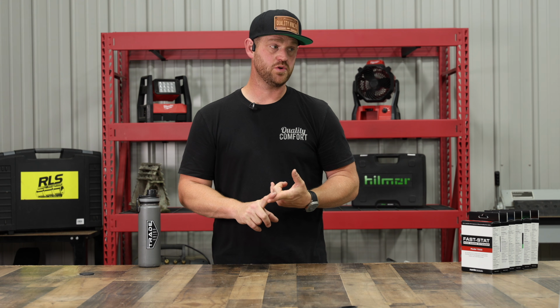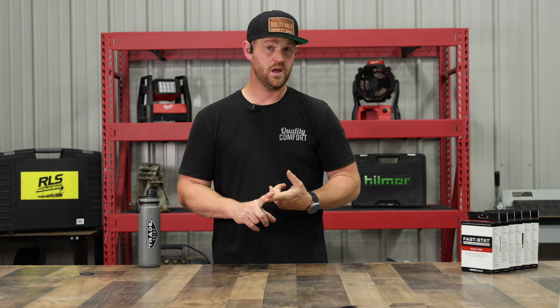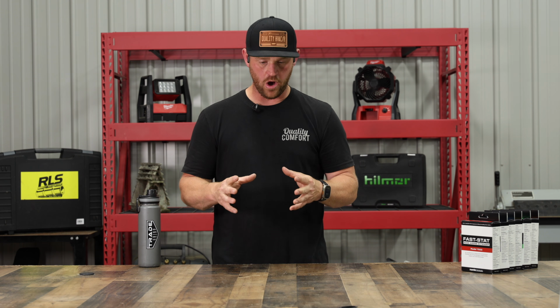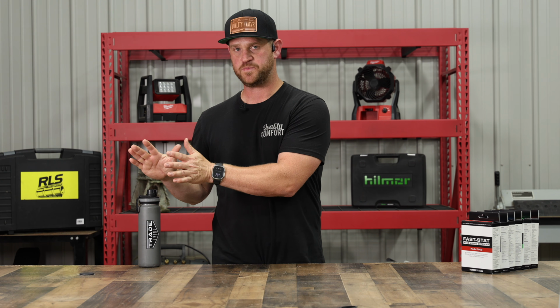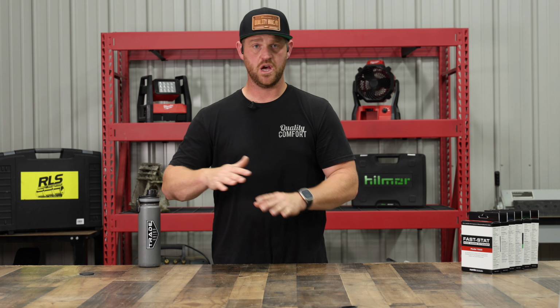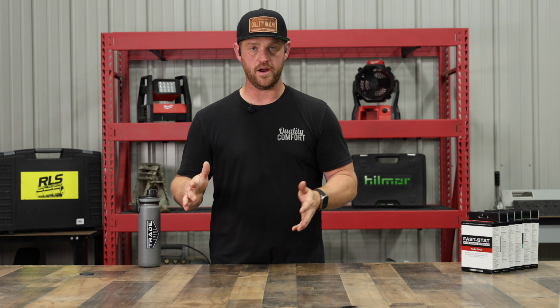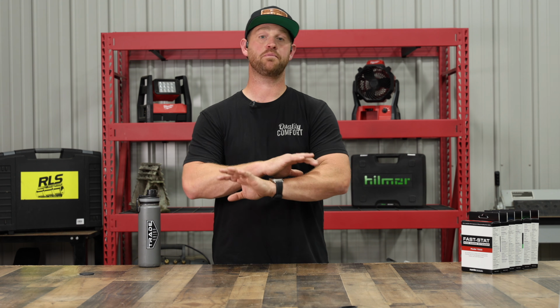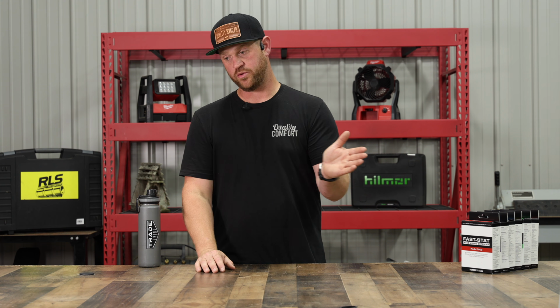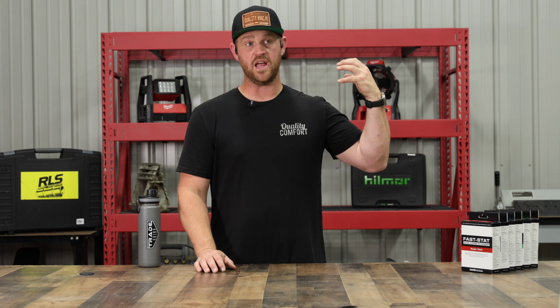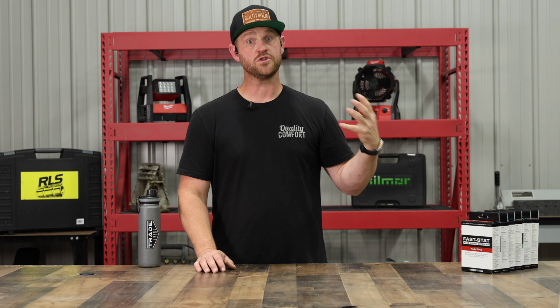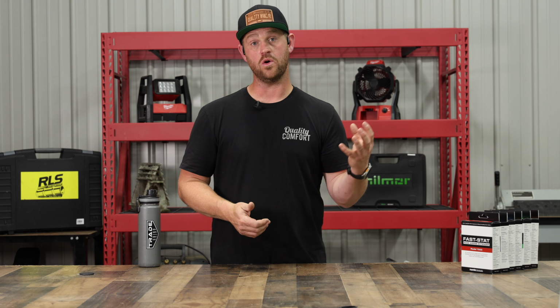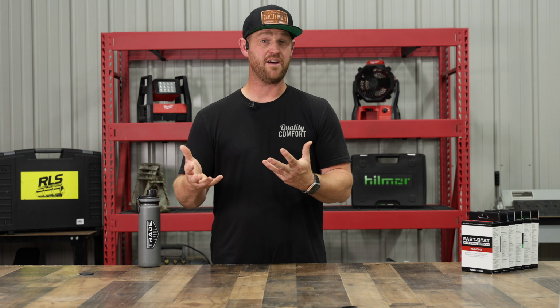So going back, you have 24-volt controlled, we have communicating, and we also have what they call VRF. Now we're only talking about variable speed systems, right? Because single stage and two-stage are pretty straightforward, not a whole lot to talk about there. With variable speed equipment, there is a plethora of options out there. We talked about the 24-volt controlled systems that are typically a ducted air handler. Those are really good for retrofits. If you already have a split unit and you want to go to a high efficiency unit, you can go with that type of system because you're already going to have pretty much everything in place.